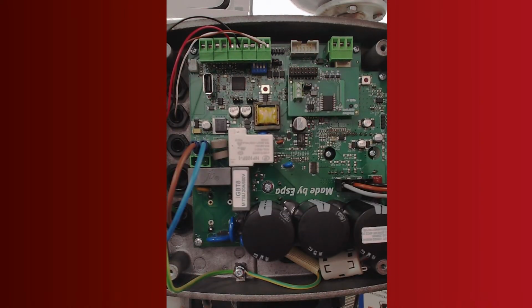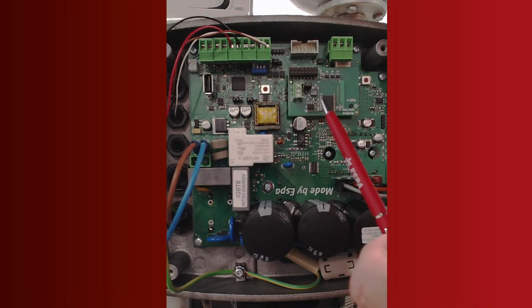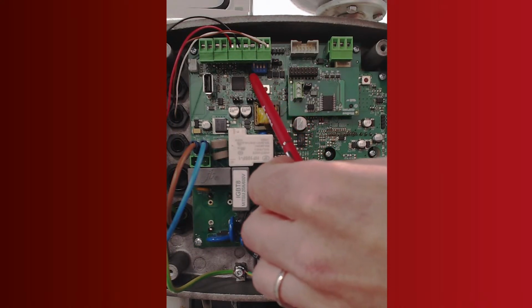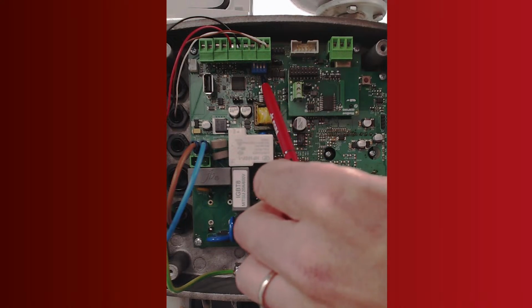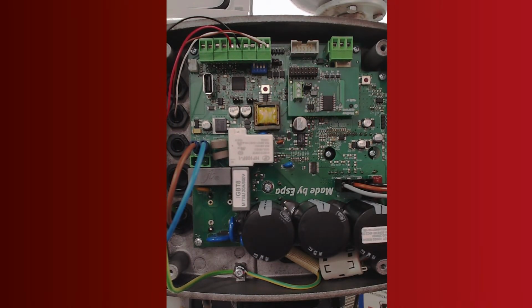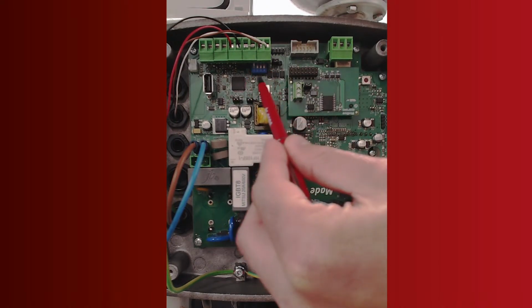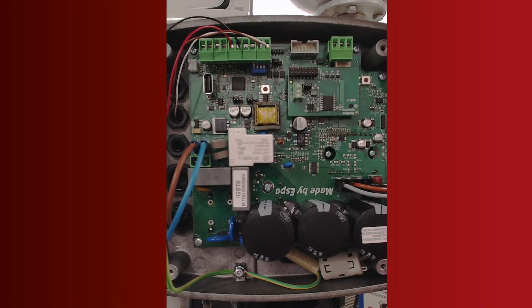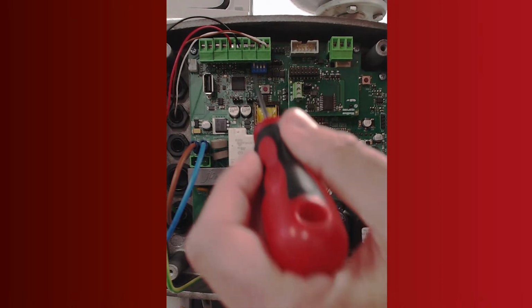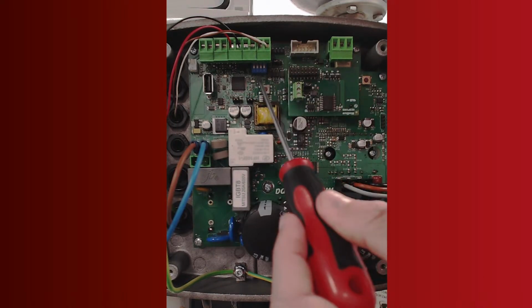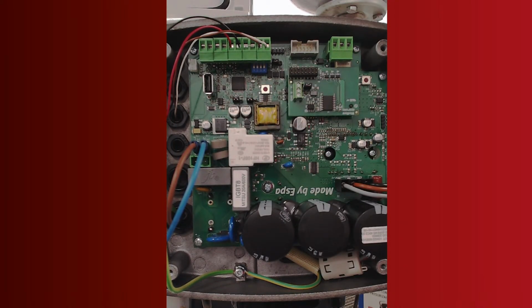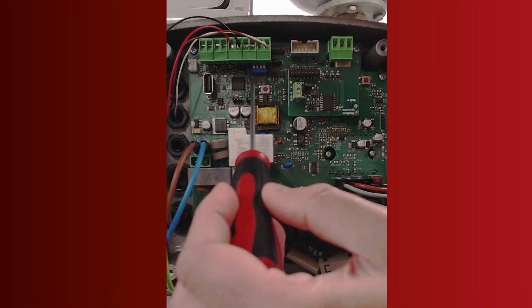So this is the inside of a single phase Speedrive, single phase in, 3-phase out. And these are the parts we have to take into account when we replace the Speedrive. Very important: this blue piece over here is the micro switch, and it indicates whether the pump is master or slave. In this case, position 1 is on, so it indicates it is slave number 1. Normally it comes with all the micro switches off. If you buy a new Speedrive, it will come like that. But if you have to replace slave number 1, it has to be set accordingly.